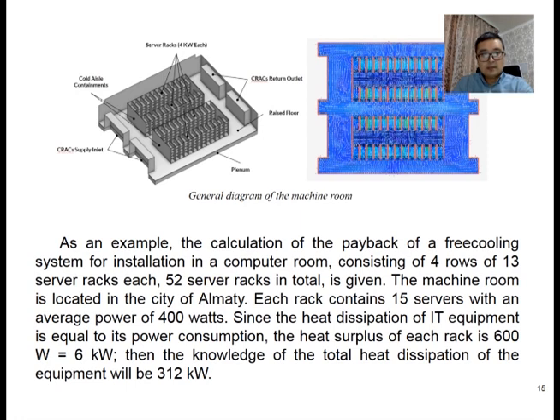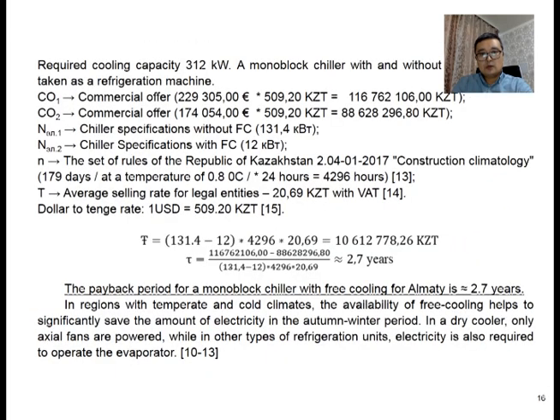The machine room is located in the city of Almaty, Kazakhstan. Each rack contains 15 servers with an average power of 400 watts. Since the heat dissipation of IT equipment is equal to its power consumption, the heat surplus of each rack is 6 kilowatt. Then the total heat dissipation of the equipment will be 312 kilowatt. Required cooling capacity is 312 kilowatt.